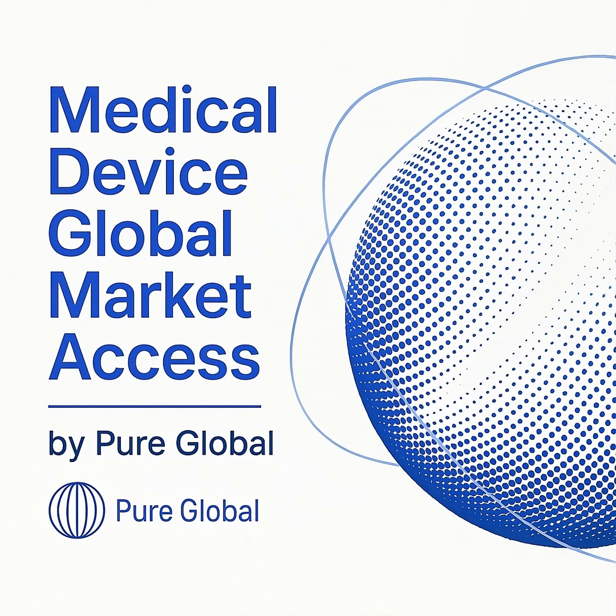First, let's clarify a critical distinction that often causes confusion: the difference between a medical device establishment license, MDEL, and a medical device license, MDL. The MDL is a license issued for a specific product, authorizing the sale of a particular Class 2, 3, or 4 medical device. The MDEL, however, is not for the product itself. It is a license for the establishment, the company, to conduct specific activities in Canada. These activities are importing, distributing, or, in the case of Class 1 devices, manufacturing for Canadian sale.